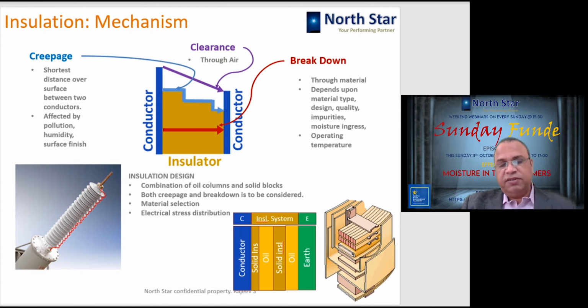So when we have this insulation system, it gets affected in three ways. One is breakdown through the air, which we call clearance. Okay, this is happening through air. Second is the breakdown where the insulation material is breaking down and becoming conductive due to the amount of voltage stress it is subjected to.